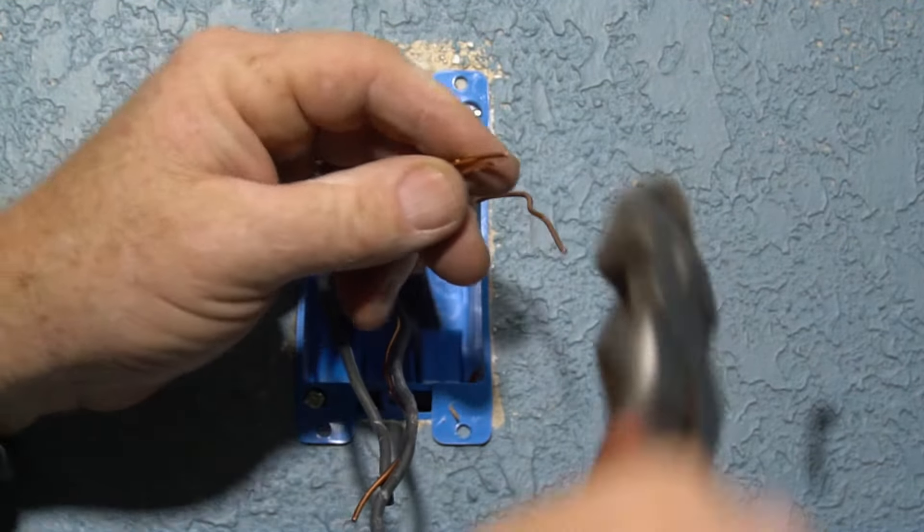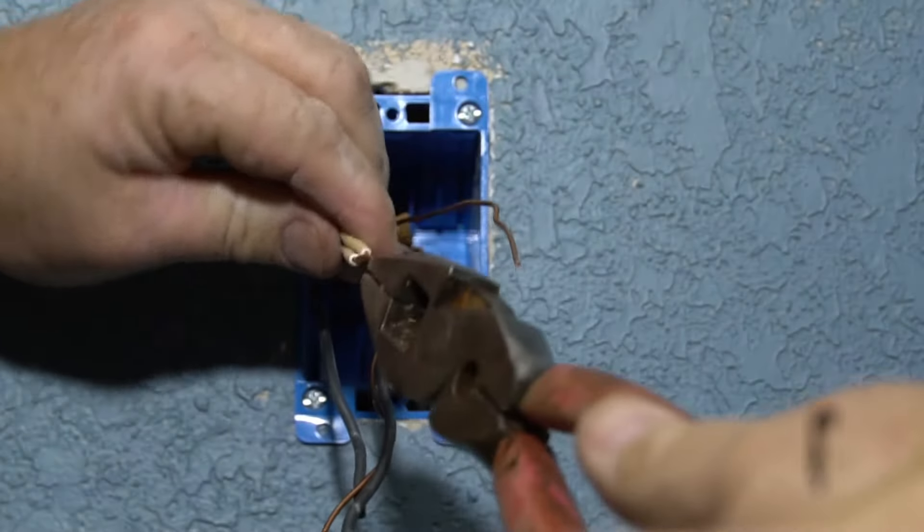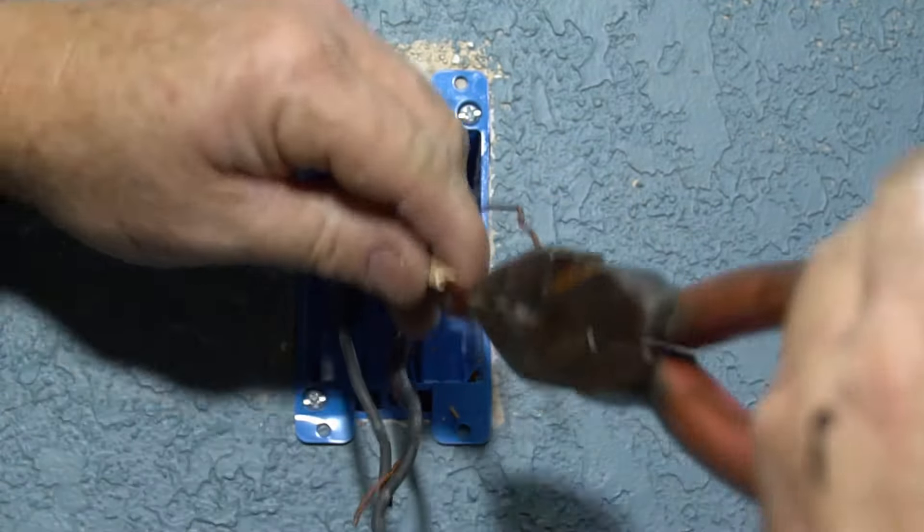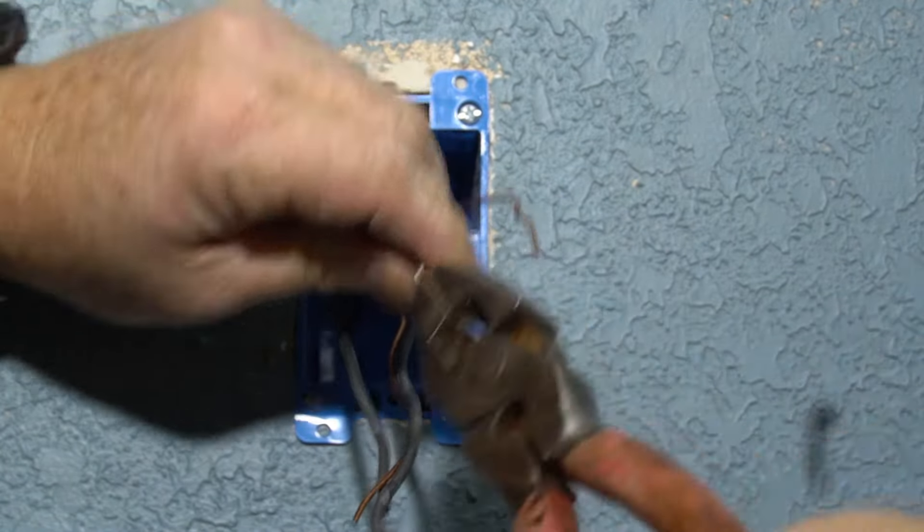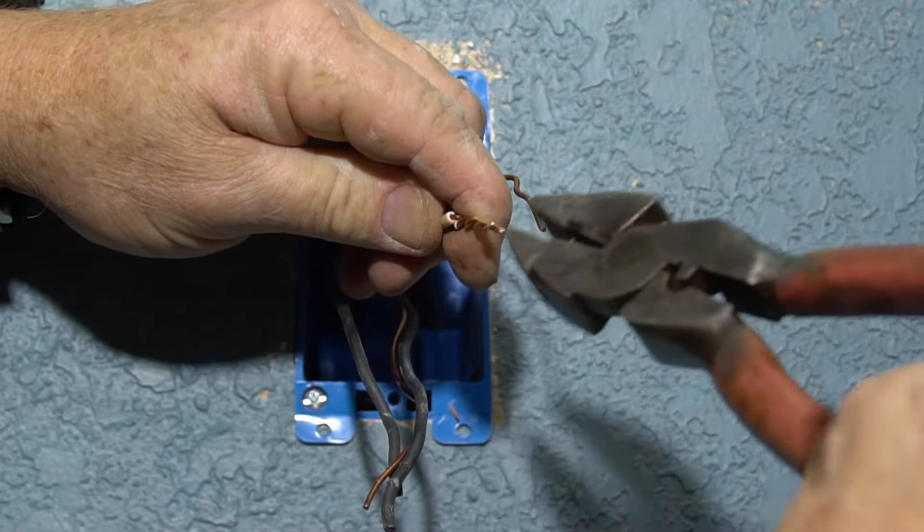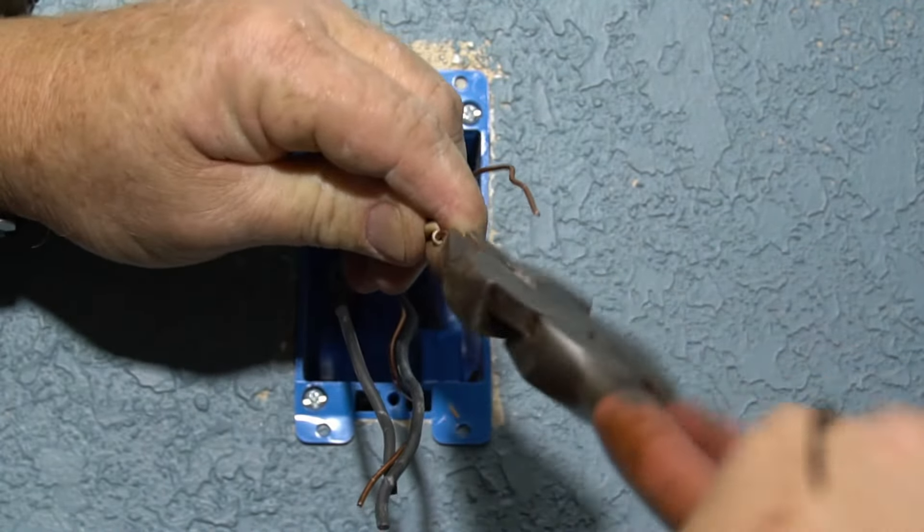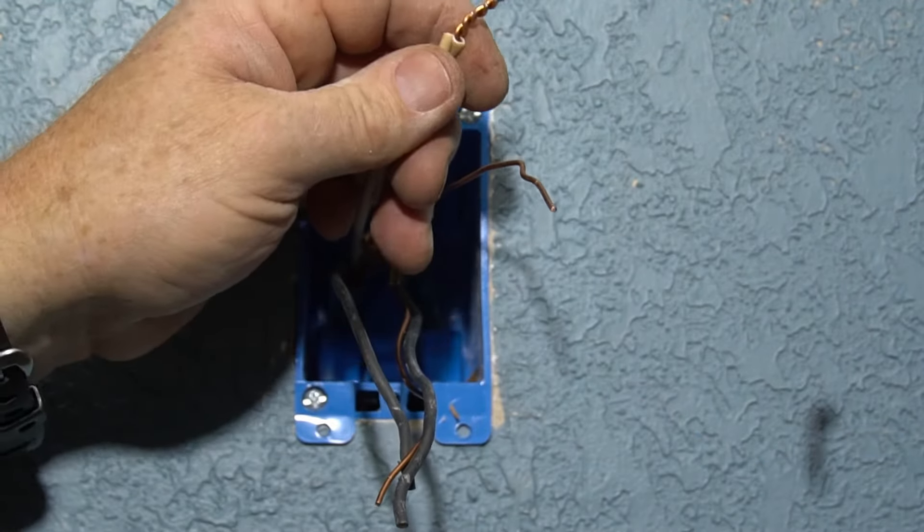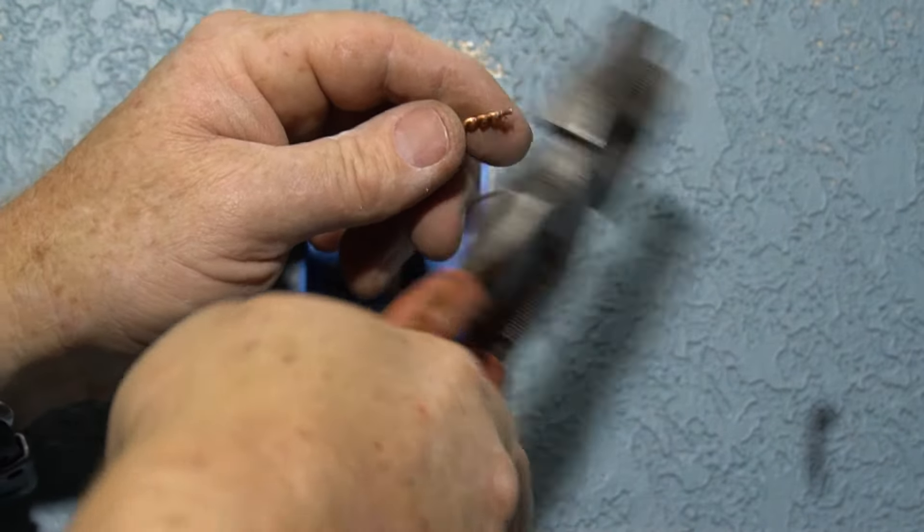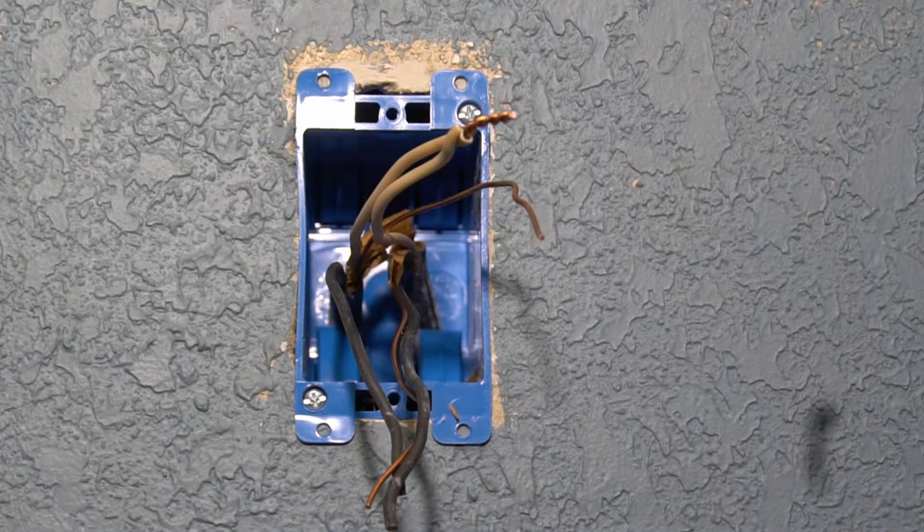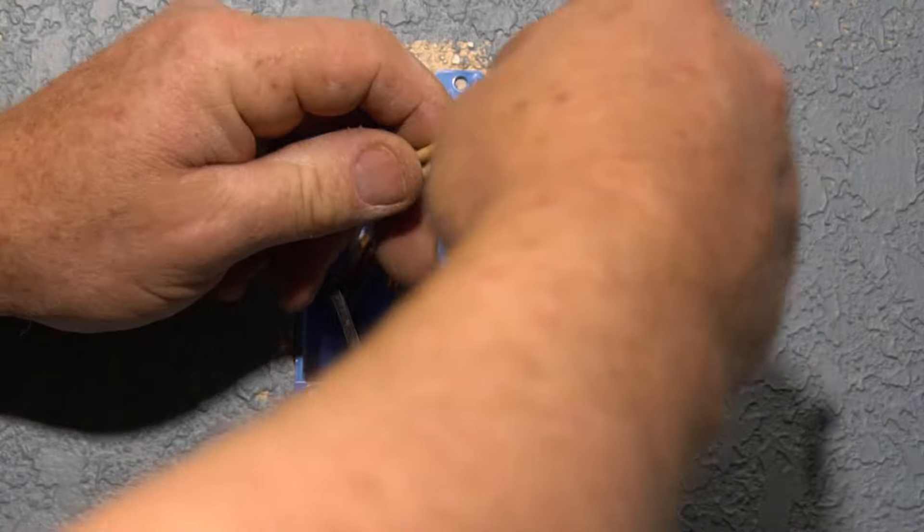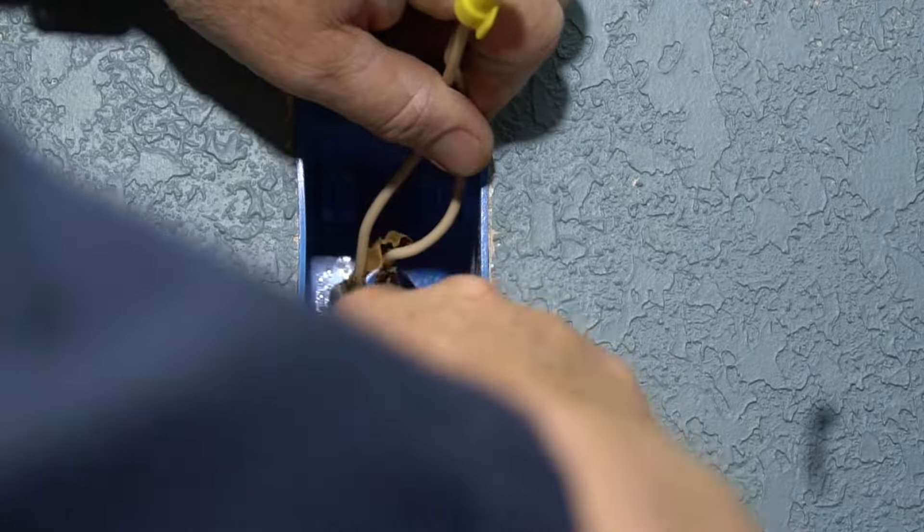Take my linesman pliers here and going clockwise, you want to twist these things together really good because you want to make sure you have a good neutral contact. Okay, get you several good wraps where it's real tight like that, trim off the end. Because this is 14 gauge wire, I'm going to be using a yellow wire nut and screw that baby down on there like so. Okay, so now that we've got the neutrals wired together...